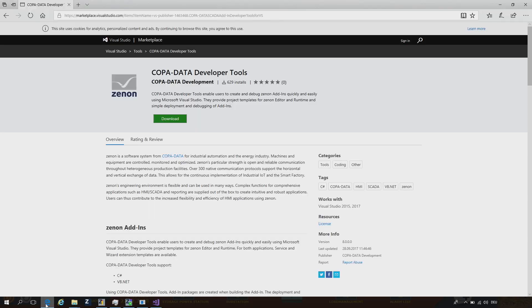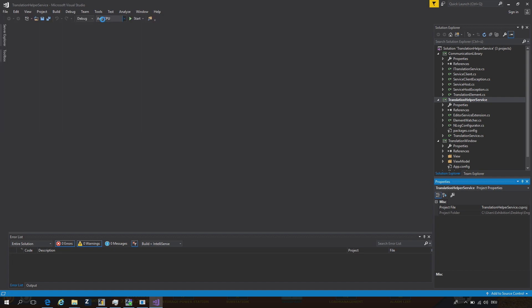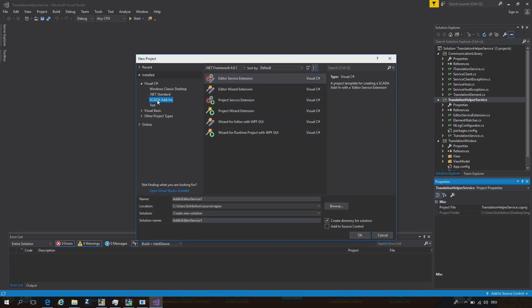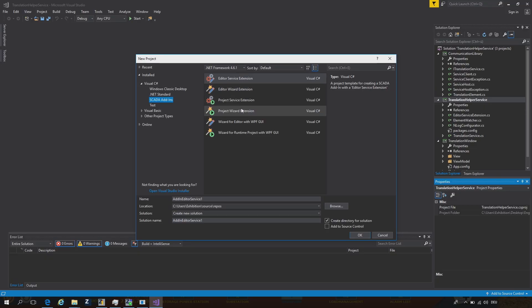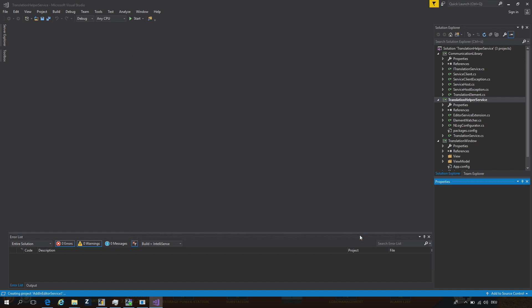For the Visual Studio integration, you will need the COPA-DATA developer tools, which you can download from the Visual Studio Marketplace. This extension modifies your Visual Studio installation and adds certain templates that you can use to create add-ins. You have the possibility to create a new project and there you find the SCADA add-in templates. You have four different types: the editor service, editor wizard, project service, and the project wizard. There are also two additional templates which come with a predefined WPF template. From this dialog, you can create a new project and then start coding your add-in.